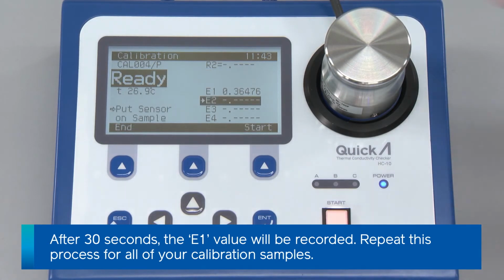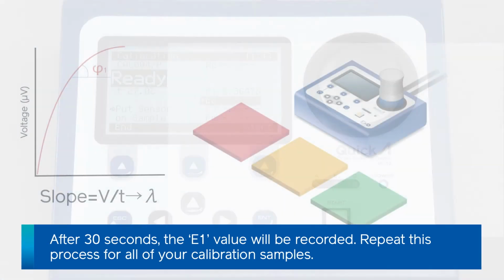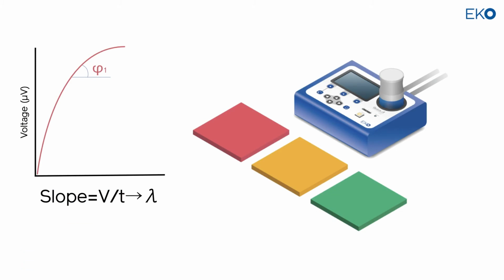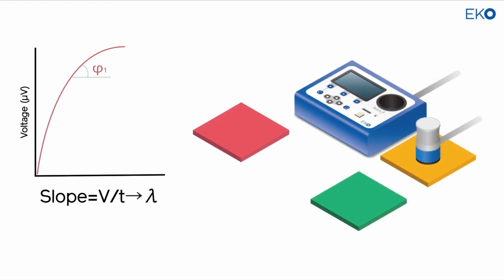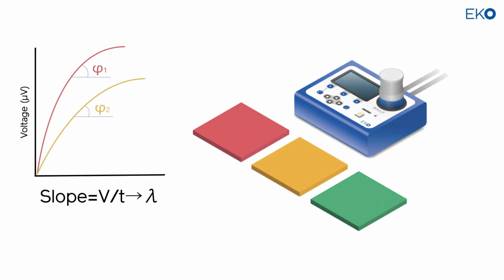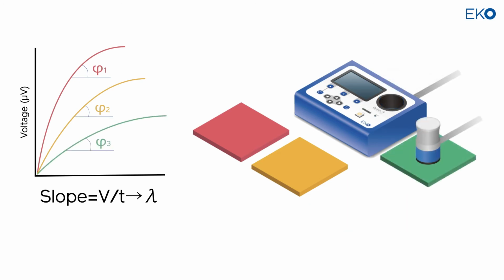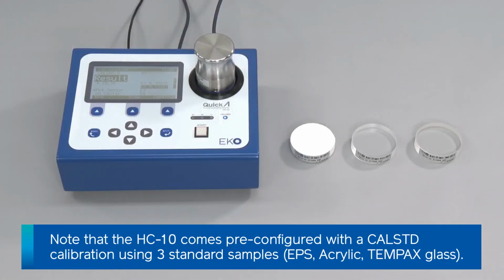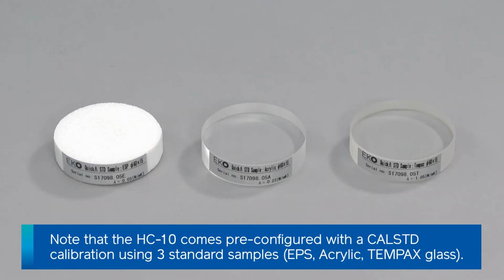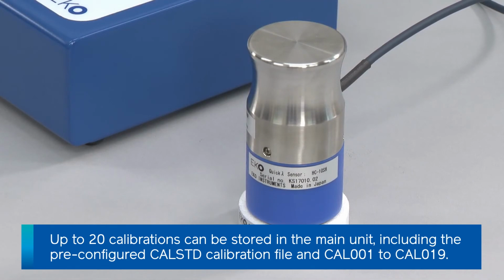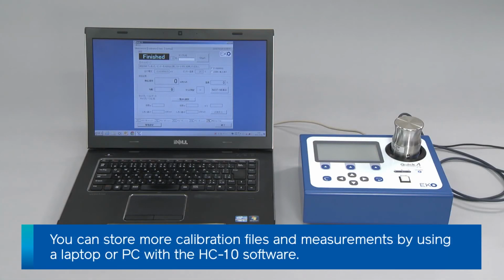During calibration, the HC-10 measures and calculates heat transfer. In this case, we have 3 samples, so we can see 3 plots and 3 E values being recorded. From the 3 recorded values, a calibration curve is then plotted. This curve will later be used to compare against during measurement to determine the thermal conductivity of your test samples. Note that the HC-10 comes with a pre-configured calibration file using the EPS, acrylic, and TEMPAX glass samples. These are used to check the condition of the sensor head. Up to 20 calibrations can be stored on the main unit, and when using the PC software, you can store even more.